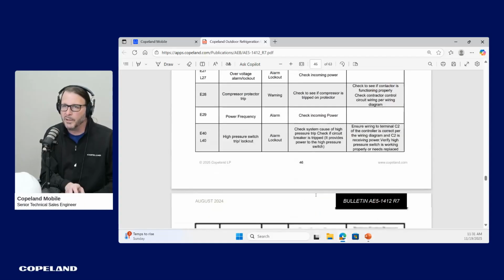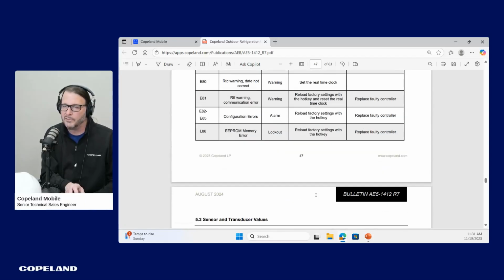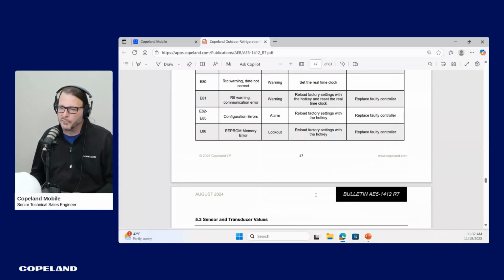As James mentioned, there are a lot of different codes on the X-Line controller. It's a very, very, very sensitive controller. Most of the time when I'm working with folks using X-Line, if they don't see some type of code on their controller, then typically their problem is located outside of the condensing unit.